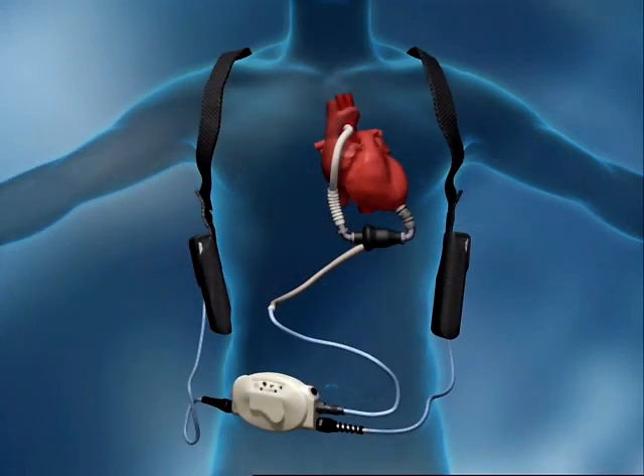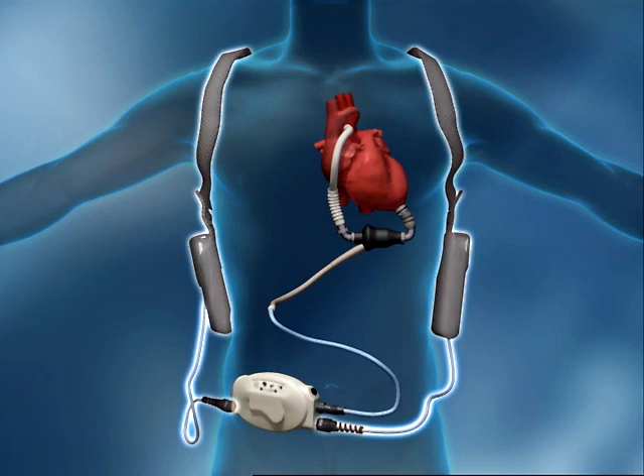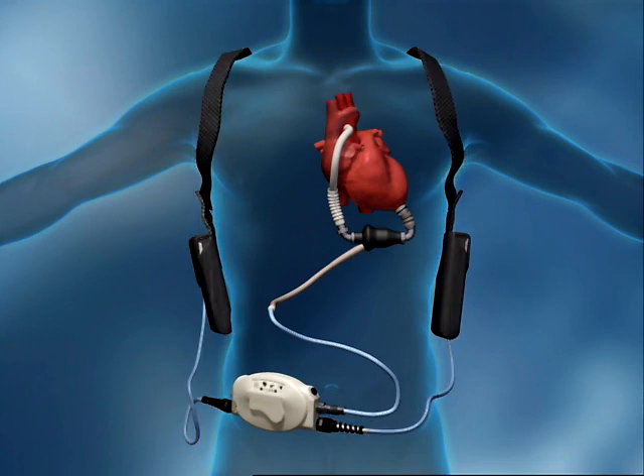The external system components of the HeartMate 2 include a small, flexible percutaneous cable that provides power to the pump and is designed to accommodate patient activity. The system controller, which controls pump operation, and the batteries, which may be conveniently worn in holsters and enable the patient to resume normal daily activities. The HeartMate 2 also shares the same equipment platform as the HeartMate XVE, which includes the PBU, system monitor, and display module.